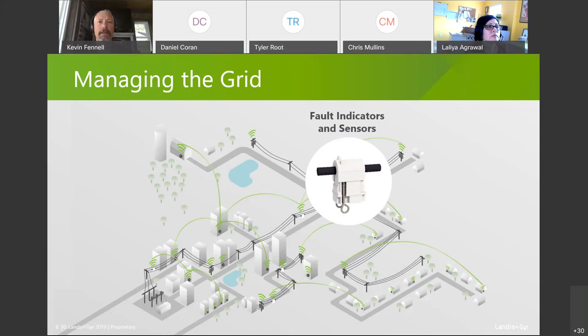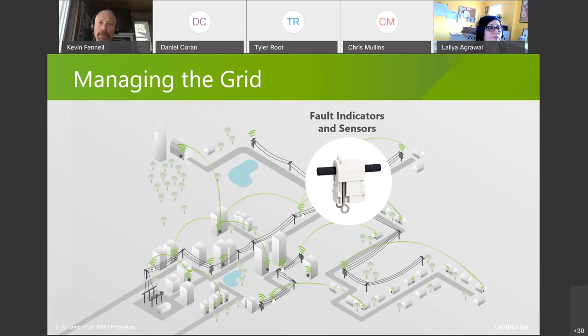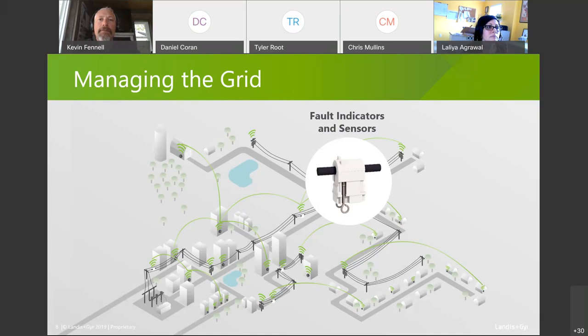Then AMI put a communication medium in the fault indicator sensor. Now it's able to capture not only that faults occurred and how many, but also give you waveform capture and signature analysis. You now know if it was a tree event that caused it, if it was an animal or bird, if it was a transformer failure, and you can identify faulty insulators and do preventative maintenance. This device became extremely valuable by combining communications with sensing capability and high processing power for signature analysis. Once you bring that level of processing power into the meter, you essentially put these sensors at every home. You can bring this data back and analyze it at the enterprise layer to make very good decisions for planning, preventative maintenance, and operations.